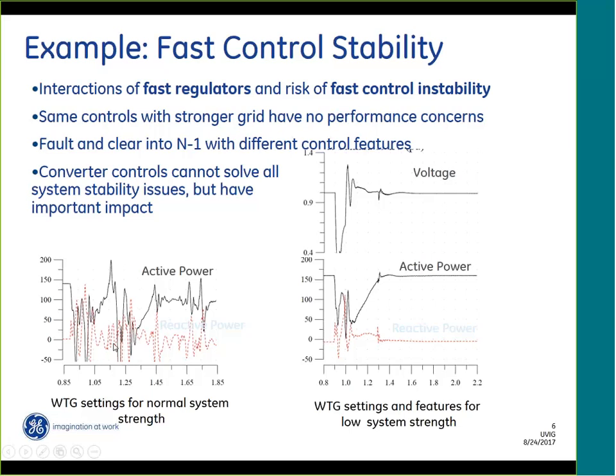In this particular case, it was possible to resolve the problem. What you see on the right is the same contingency now with a different configuration of the wind turbines, more specific to low system strength operation. So these oscillations in this case could be solved by modifying the settings. The important observation here is that if you would have the same SVC and the same wind plants connected to a stronger grid, you don't see this type of interactions. So this is really a system phenomenon in the sense that it depends on the different controls, and also depends on how strong the system is. The weaker the system is, the more likely to have an interaction between the different power electronics connected to the same network.